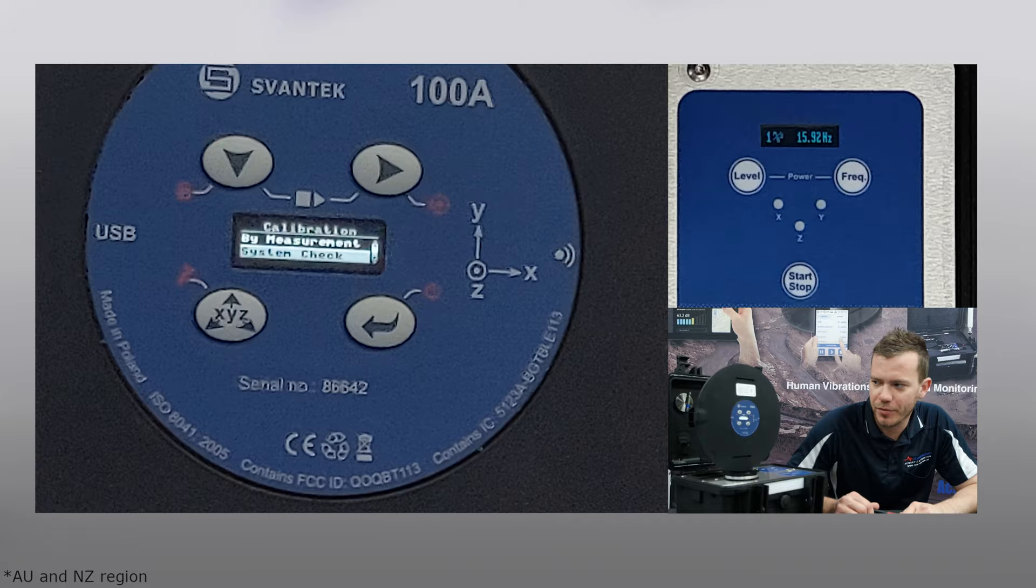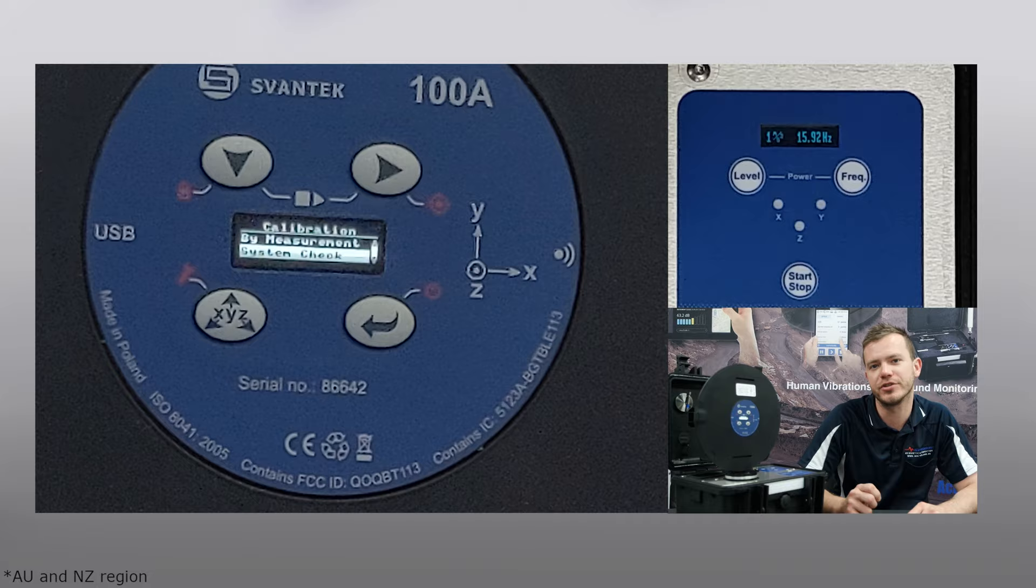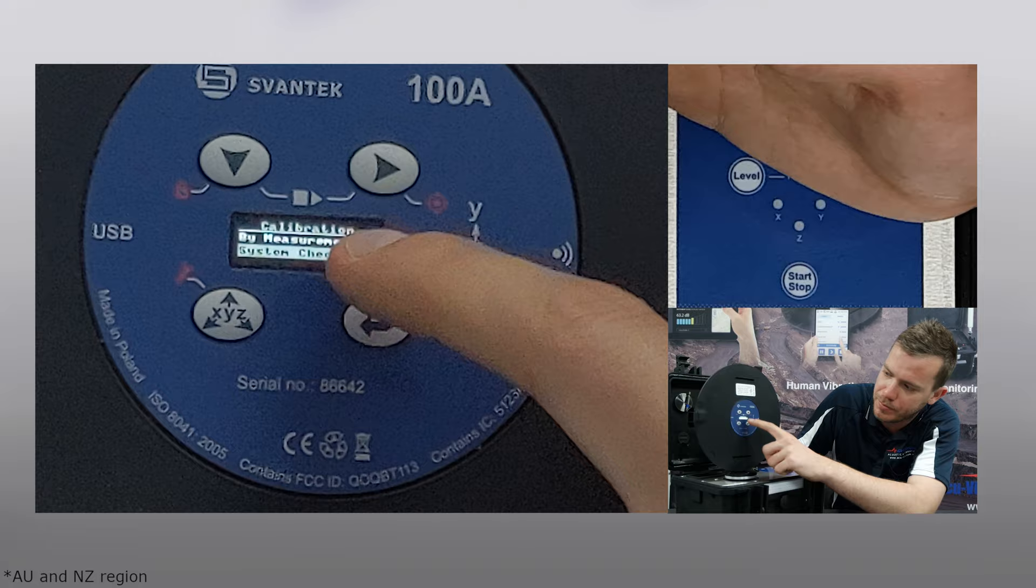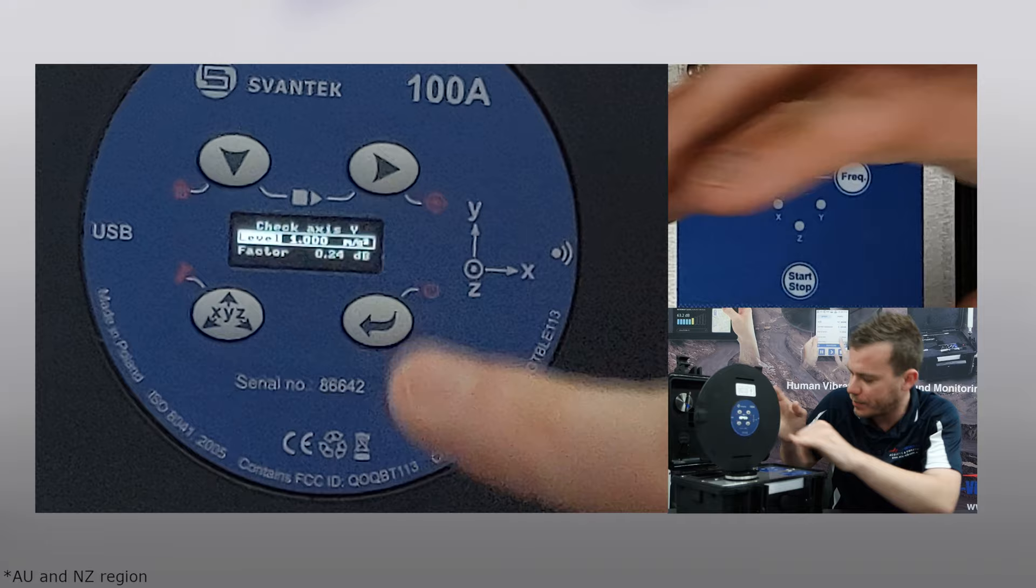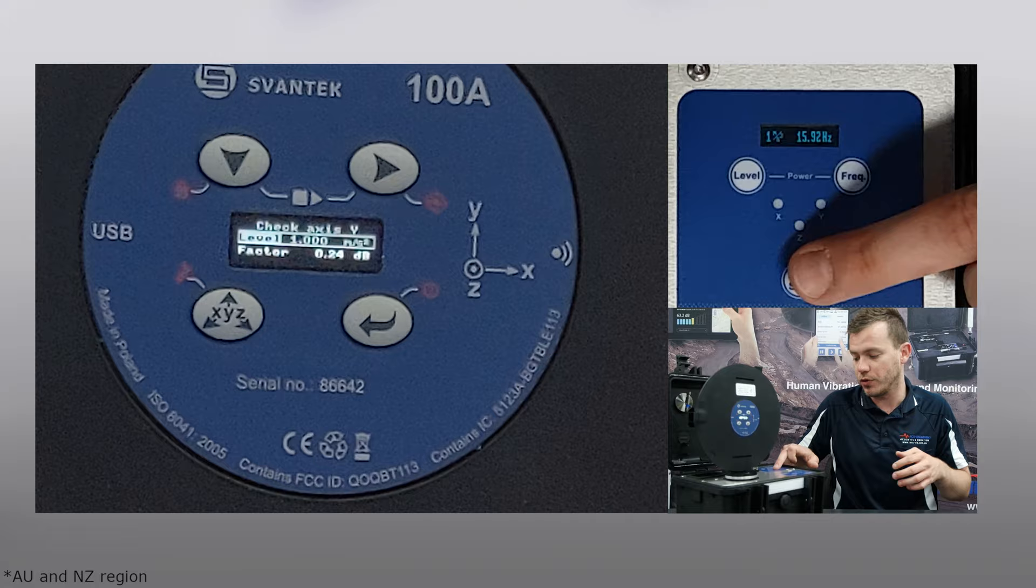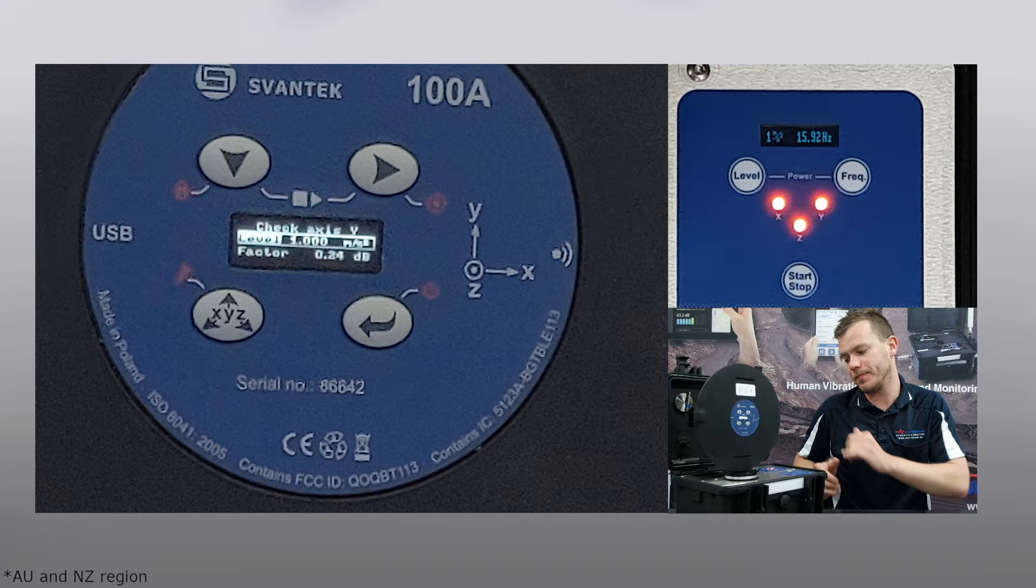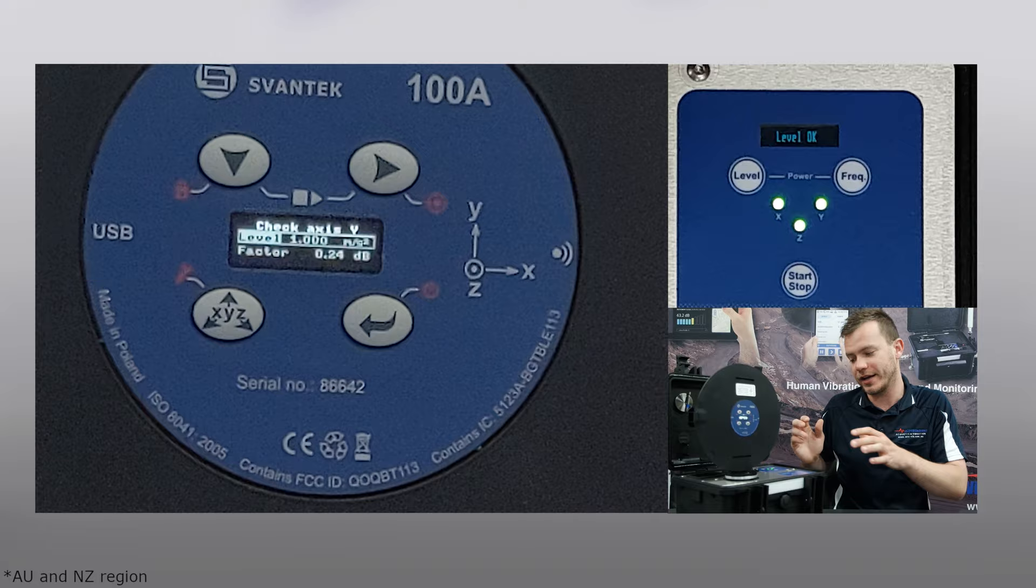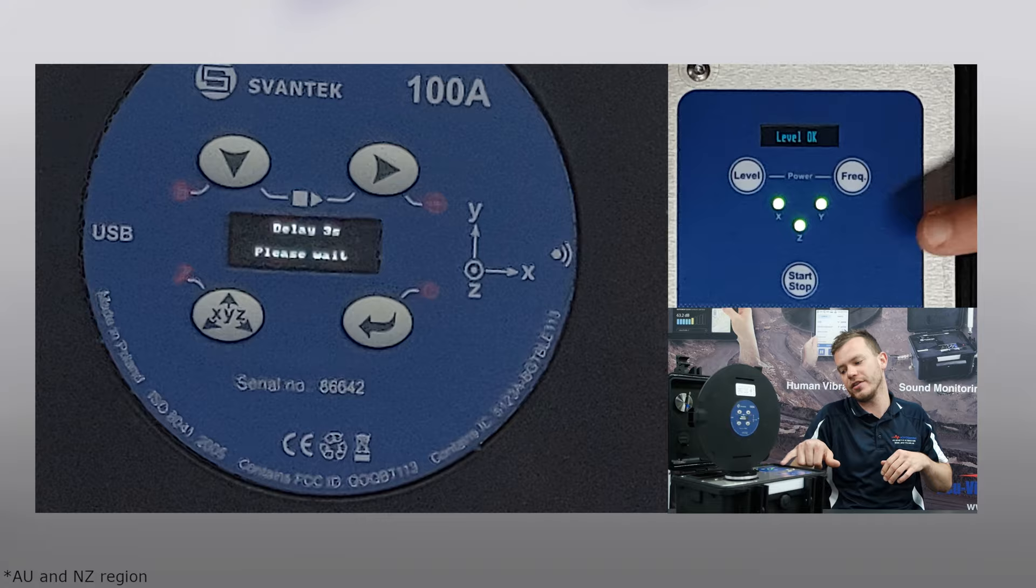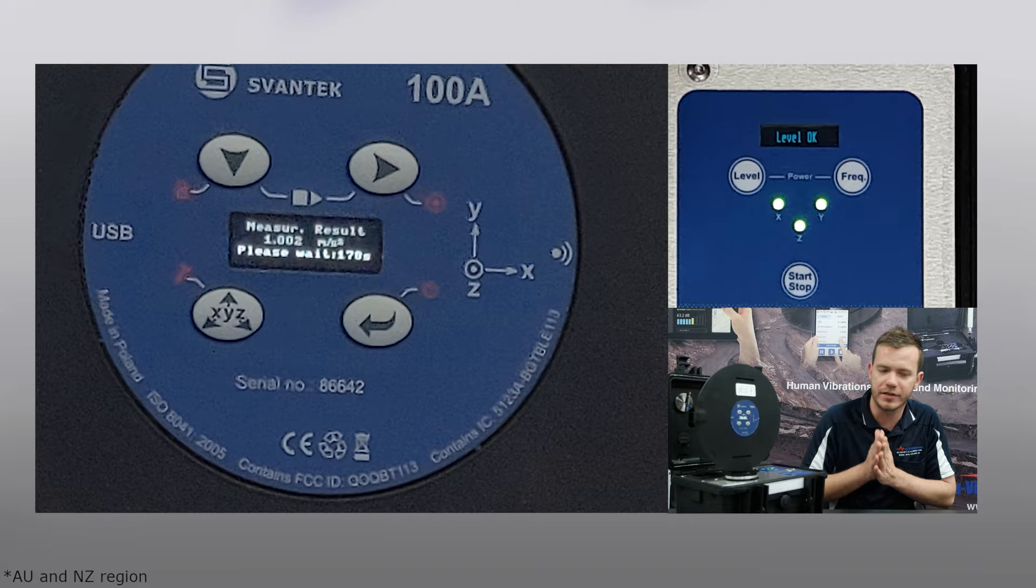Now that we've done a calibration, a standard measurement calibration with the shaker, I'm going to do an in-situ check, which is basically a system check that the instrument has in its menu. Once again, hold the calibration button, but instead of by measurement, I'm going to do by system check. I'm going to go down to the same axis we were just looking at. Press enter and we have our level, 1 meter per second squared like the shaker is displaying. I'm going to start the shaker first to give it time to auto settle itself. When you press start there might be a little bit of slight movement, but at least the shaker is already shaking. Wait for these lights; 30 seconds is an allowable time. Once it's green I'm going to press start. We're waiting for the shaker to stabilize. It's all green. Press start and there we go. As you can see, the red lights are flashing but they come straight on green, giving more time for everything to stabilize before your measurement.